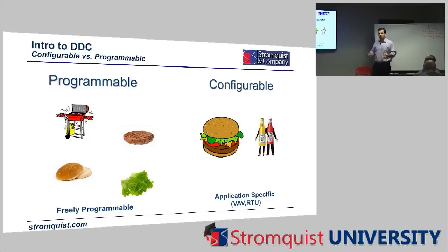I struggle with this analogy sometimes to properly make it, but essentially, if you're a configurable controller, it's application specific. So you're going to buy a controller that's for a VAV box, and it's going to come up and say, I need to know this. I need to know the CFM that the box is.